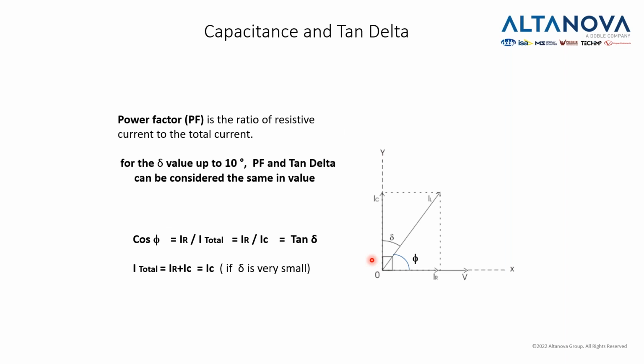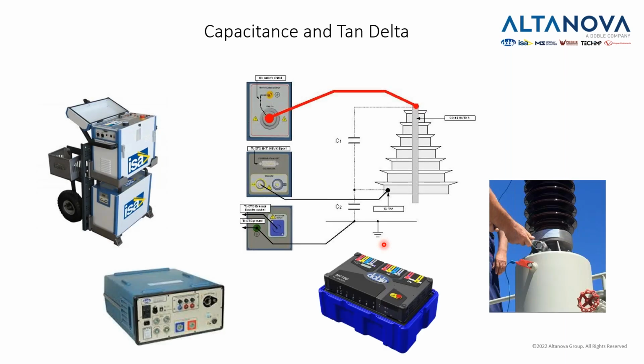Power factor, on the other side, is not IR over IC, but IR, resistive current, over IT, total current. But since this angle is very small, this vector is almost equal to this vector, which effectively means that we're talking about the same parameters. So if this angle is less than 5 degrees, and it should be, then power factor and tan delta have the same values.